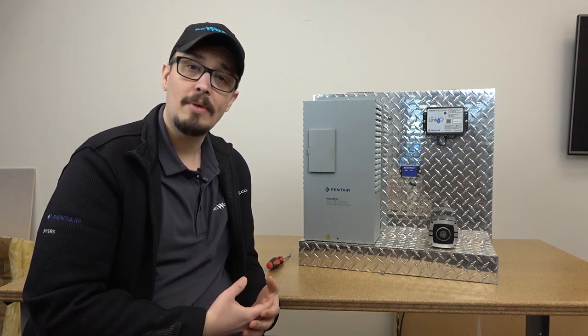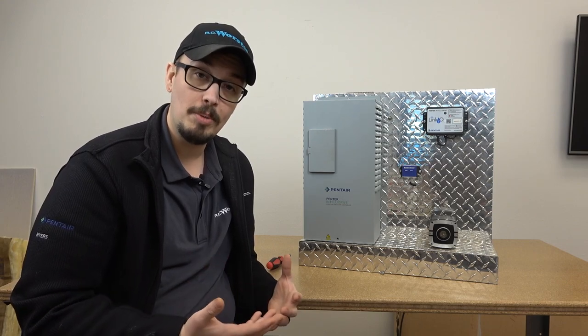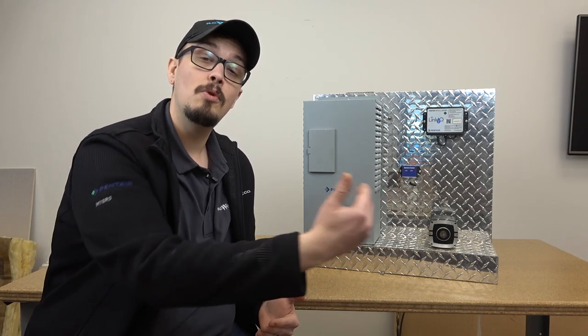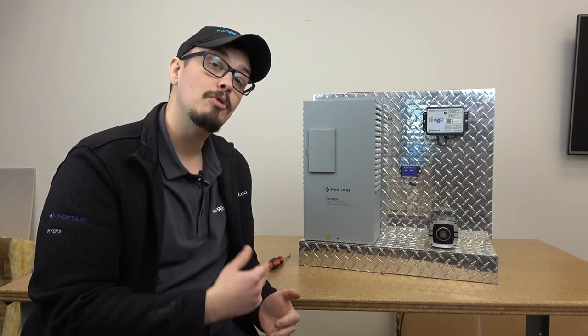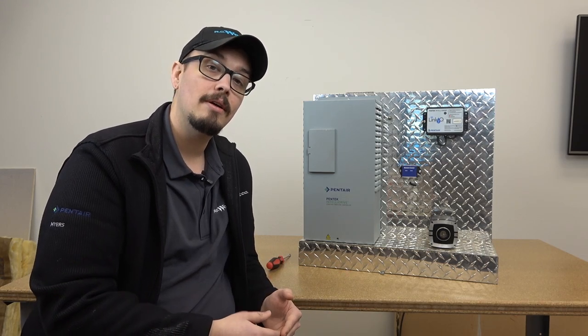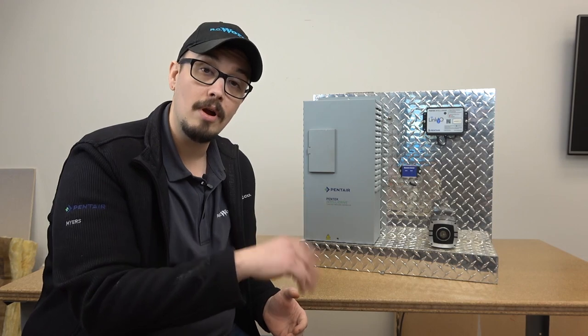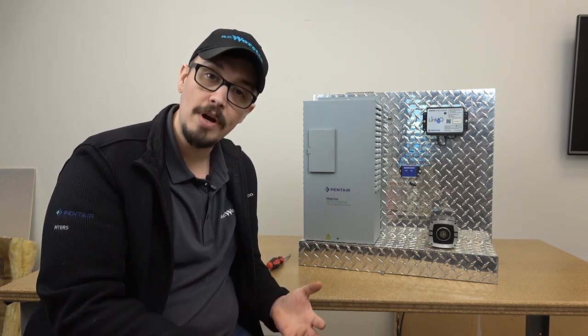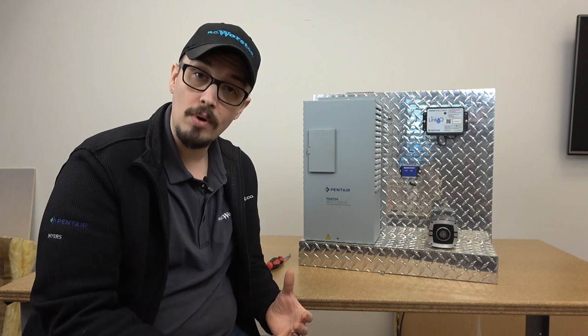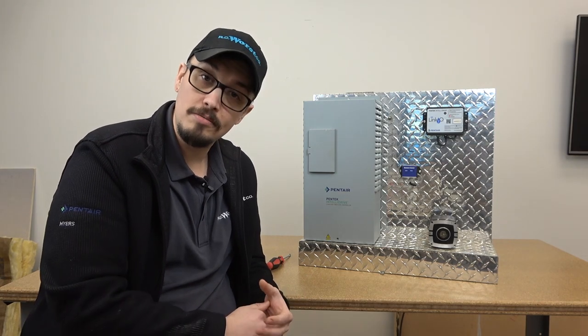One thing to keep in mind — they'll run single-phase or three-phase motors — is that the current rating at those different horsepower ranges is important. For example, a PID 20, though it can run a three-phase two-horsepower motor, is not able to run a two-horsepower motor on single-phase. So make sure you check the specs for whichever drive you're considering. If you plan on operating it in a single-phase situation, keep in mind the amperage — especially on your above-ground pumps — so you don't exceed whatever that particular drive is rated for. Those are all going to be well-labeled and well-listed. We'll have some resources in the description below if you want to check these out to purchase for yourself.